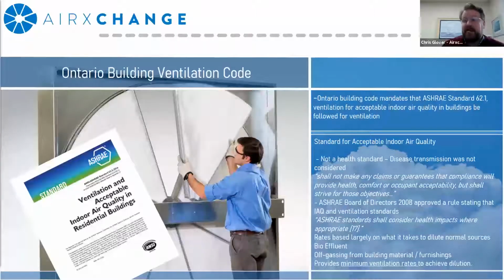Standard 62 is not a health standard, meaning that disease transmission was never considered during its development. There have been changes over the years where health-related impacts are now being considered where appropriate. However, the rates are largely based on what it takes to dilute what most people consider normal space air, which is mostly bioeffluent, contaminants from people, or sources within the space, or off-gassing from sources within the space, furnishings, or any processes that might be taking place in there. And the ventilation rate provides what the minimum rates are to achieve proper dilution. And you might see that I highlighted minimum ventilation rates because, as with most code-related mandates, the minimum often becomes the maximum. And as we're seeing with the pandemic, these minimum rates usually don't provide the best benefit during these periods of crisis.